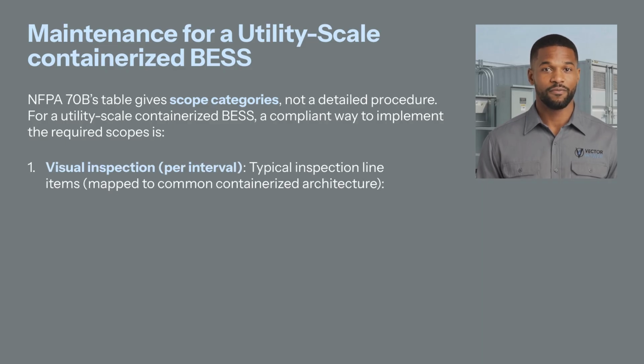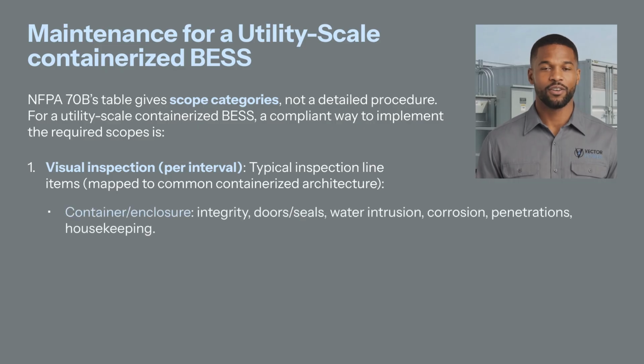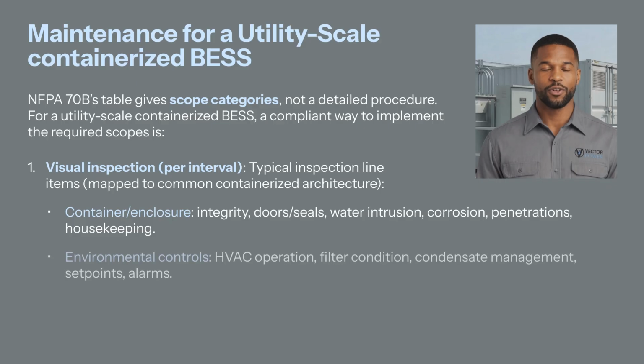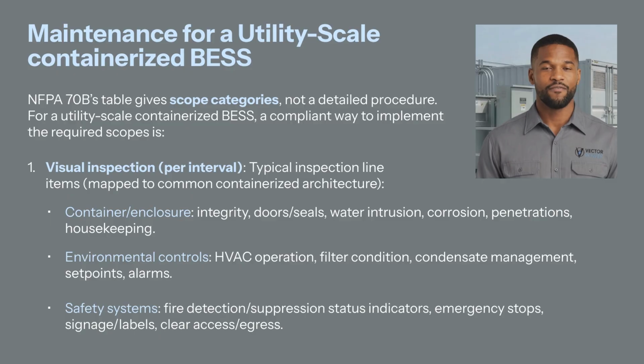Visual inspection per interval. Typical inspection line items map to common containerized architecture: container enclosure integrity, door seals, water intrusion, corrosion, penetrations, housekeeping, environmental controls, HVAC operation, filter condition, condensate management, set points, alarms, safety systems, fire detection, suppression status indicators, emergency stops, signage and labels, clear access and egress.